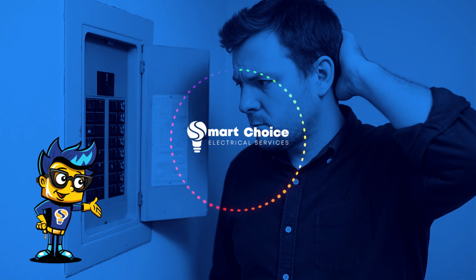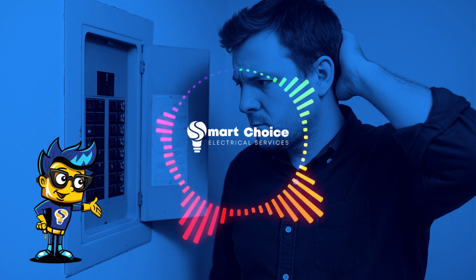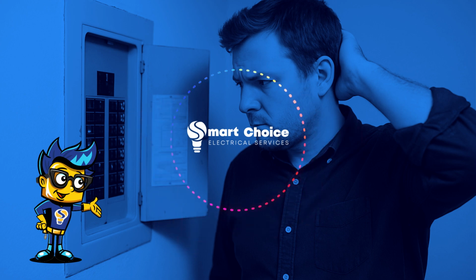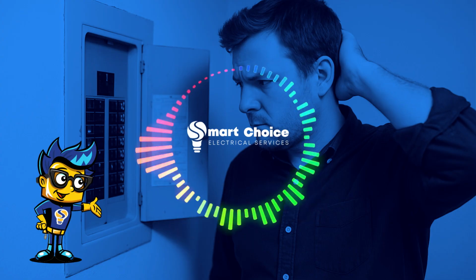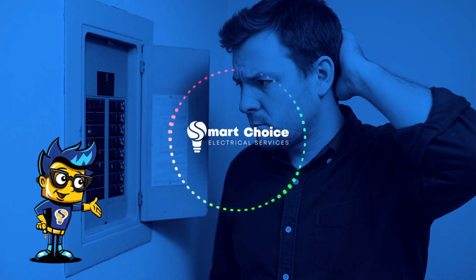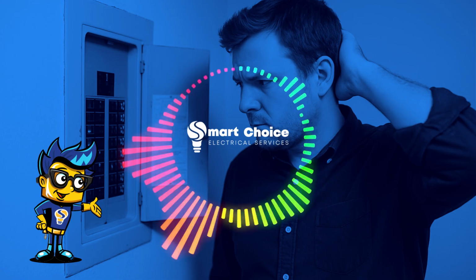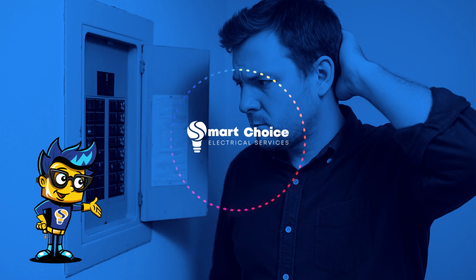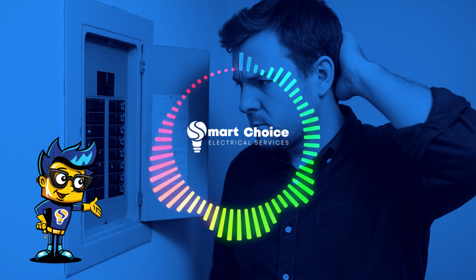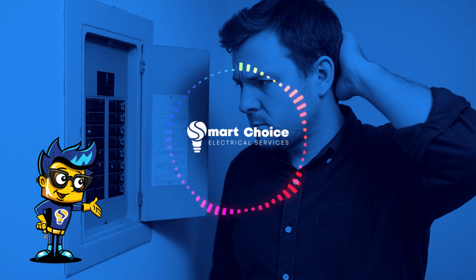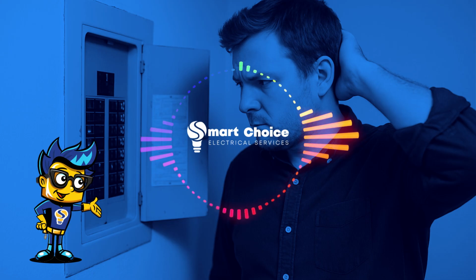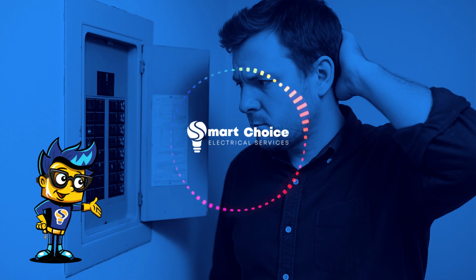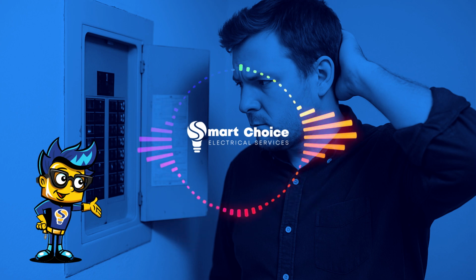Okay, let's shift to something that sounds immediately alarming: burn marks, melting, or strange smells around the panel. This is not subtle, this is a major emergency warning sign. If you see any dark scorch marks on or around the breakers, any sign of plastic melting, or if you smell something like burning plastic or ozone, don't touch anything, do not touch the panel, don't try to reset breakers. This indicates severe overheating, potentially arcing connections, a very immediate fire hazard. You need to call for emergency electrical help right away. Your safety is the absolute priority.